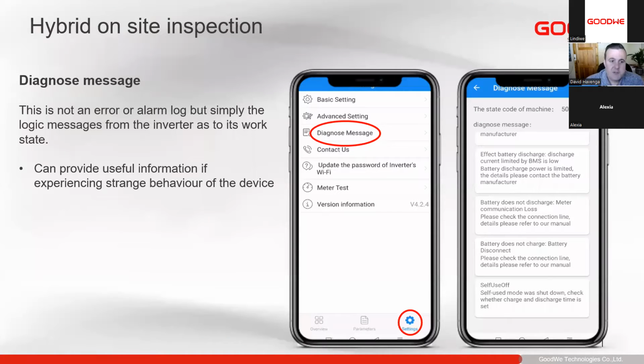Next is diagnose message. This very often gets confused with error messages. Diagnose message is not an alarm or an error. It's simply the logic operating messages. Most of it is, I am doing this because of this. I am not charging the batteries because the batteries are full. In this example, it says effective battery discharge current limited by BMS is low, so the battery is flat. Battery doesn't charge because there's no smart meter connected.